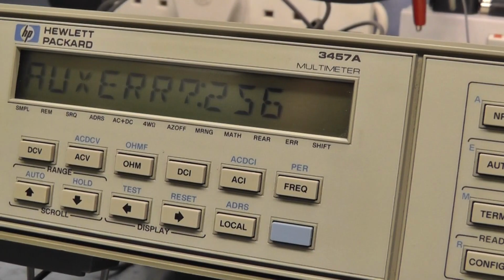Okay, let me read you what it says in section 5.17. It says this adjustment is not required unless the self-test response is hardware error and the aux error is 256. Adjust the AC converter frequency response as follows: remove all power from the 3457A, line cord and external inputs. Loosen the two screws attaching the rear terminal assembly and remove the assembly block - that's the connection on the back. Turn the instrument upside down and loosen the 6 captive screws in the bottom cover.